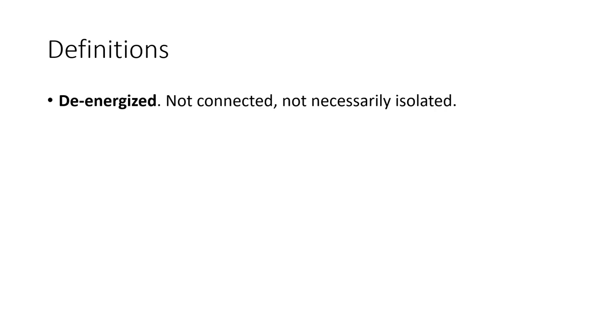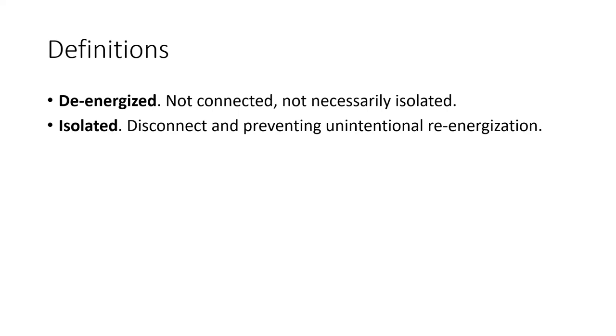First of all, just a couple of definitions that I'll be using and that you'll find in the hierarchy of controls and in many of the Australian standards. And the first is de-energized, which means the power has been disconnected, but the power is not necessarily isolated. That is, it could be reconnected at any time. But isolated means it's been locked out and tagged out, and it's prevented from being unintentionally re-energized.